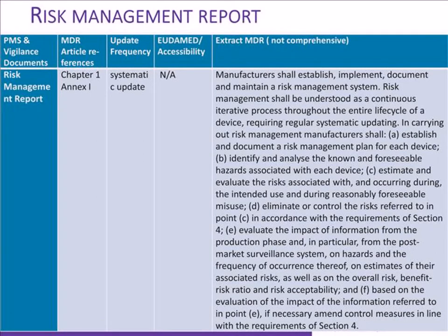Moving next to the risk management report. So the risk management reports cover the entire lifetime of the device. It's required as a risk management plan for each device covering the known and foreseeable hazards. And for this one, it's a systematic update. So systematic update needs as well that we define threshold for revision, and it needs to be periodically reviewed for update.